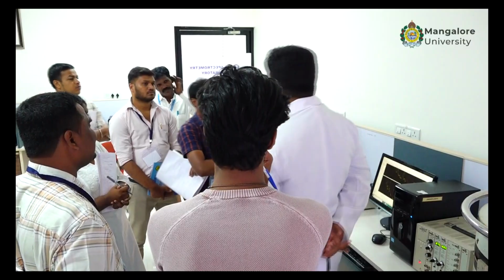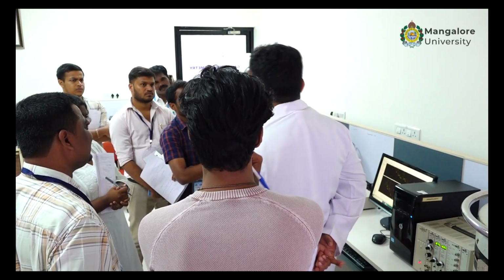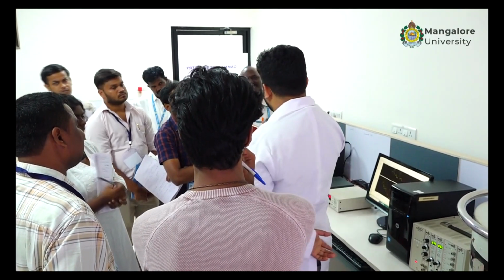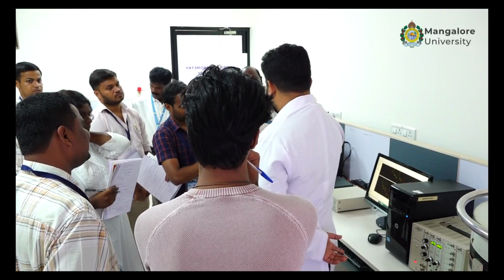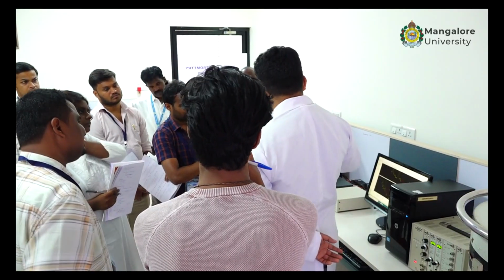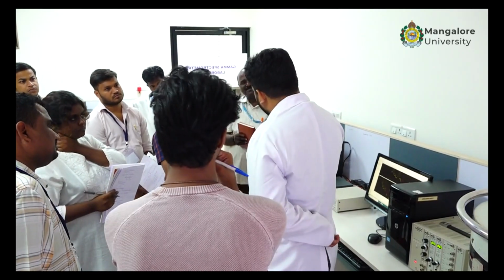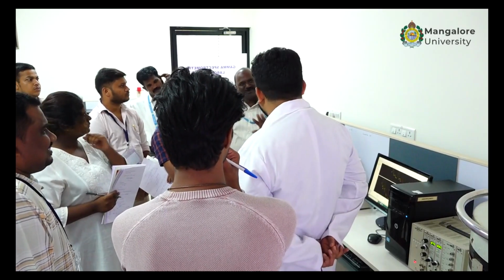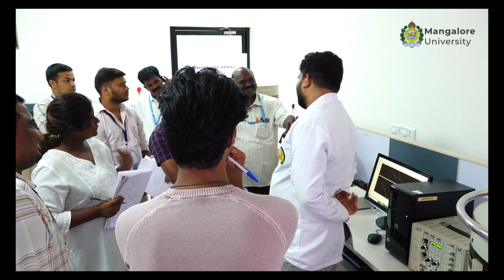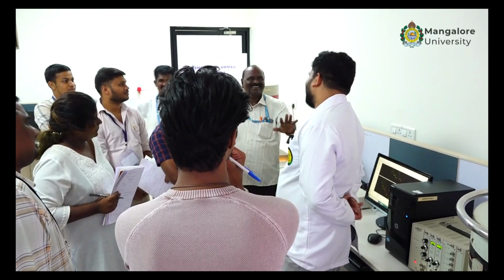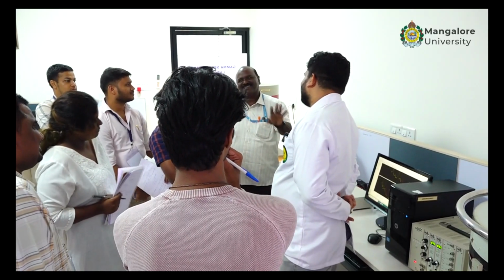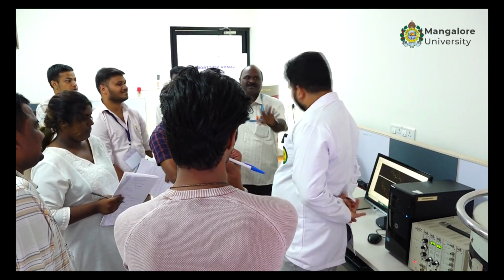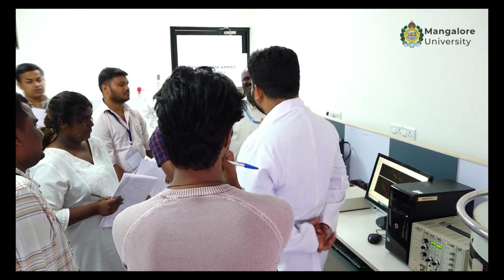You can do one simple thing: you have an IAEA standard or any certified standard, you measure the efficiency, then you keep your sample, maybe 10, 15 types, and calculate. You are using one standard. Other people are not accepting that, so that is a problem. The IAEA standard is universally accepted, by everyone.